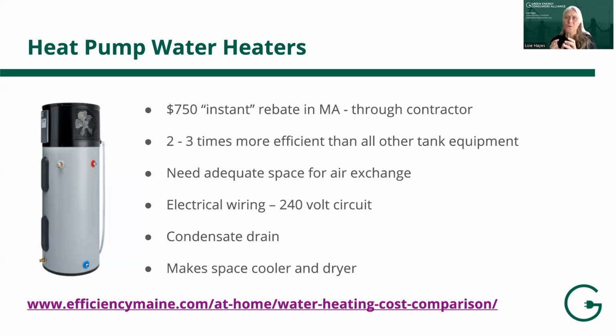You can't put these in a small utility closet because they need to be able to grab heat from a large space to be able to concentrate that heat into the hot water, give you adequate hot water. They do at present need a dedicated electrical circuit. There are plug-in varieties, but they're not popular yet. They're not really marketed here in New England, where our intake water is so cold. The economics, the operating costs of that unit get to be pretty stressful. It does need a condensate drain because as it grabs the heat out of the air, it's also going to condense water vapor that's been held in that warmer area will drop out. So that needs someplace to drain.